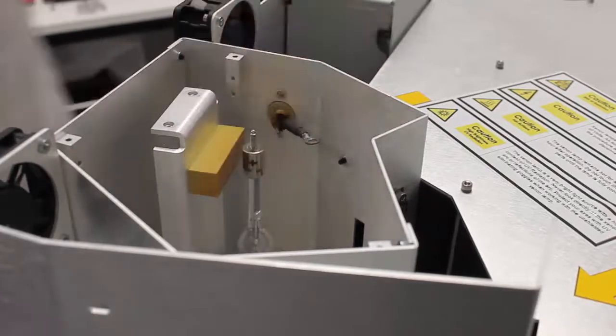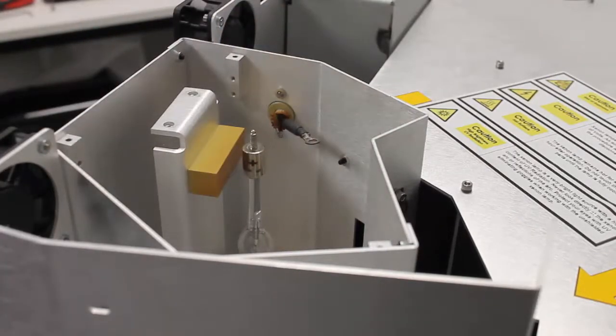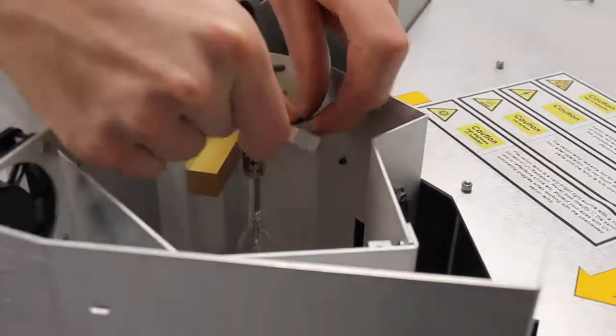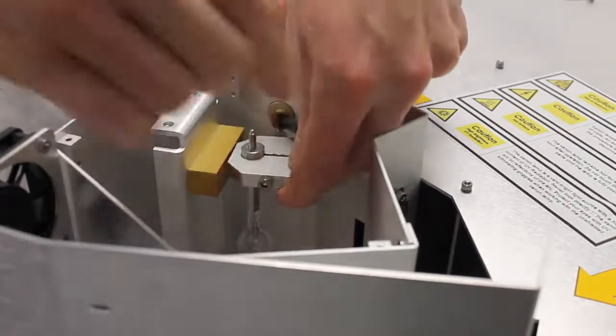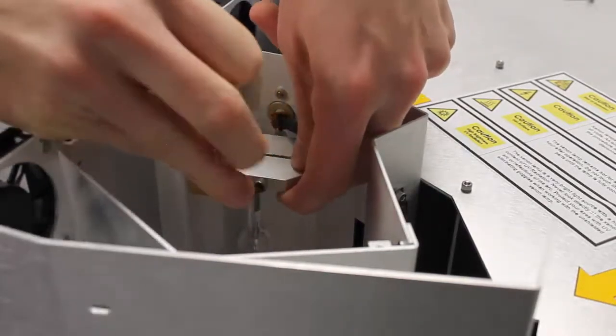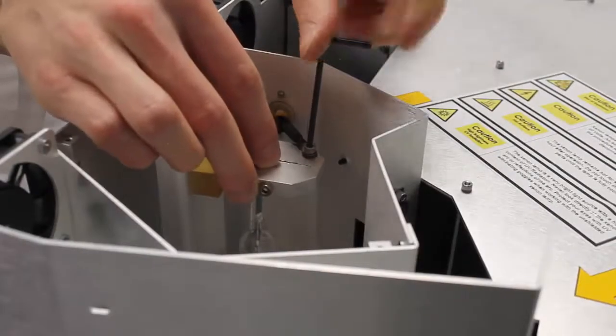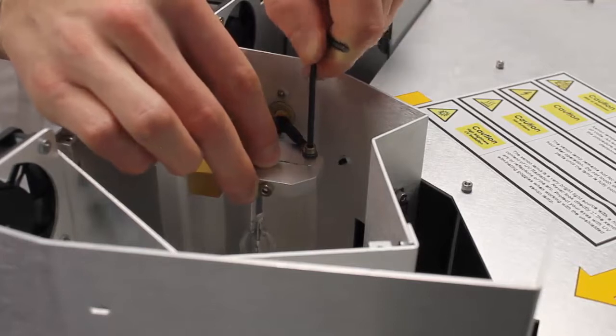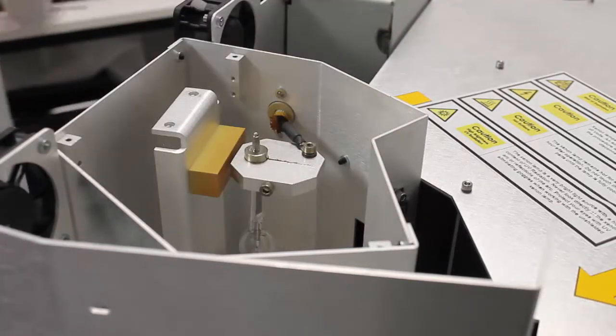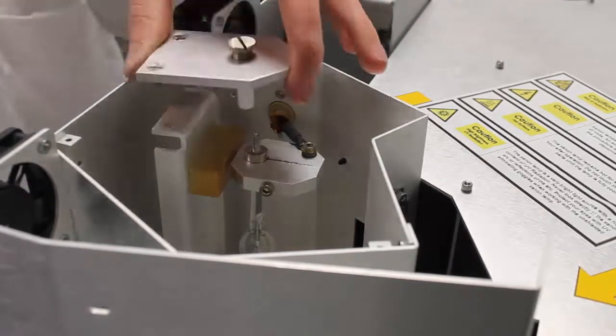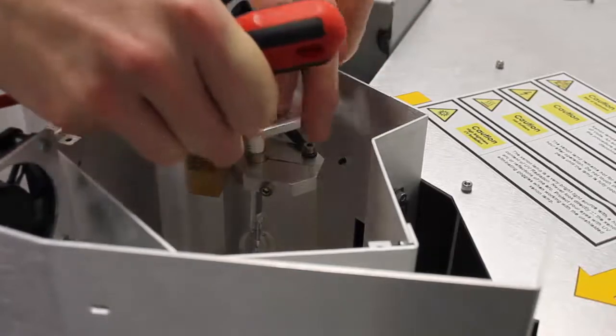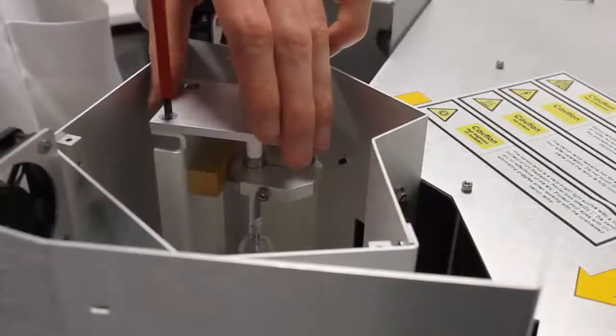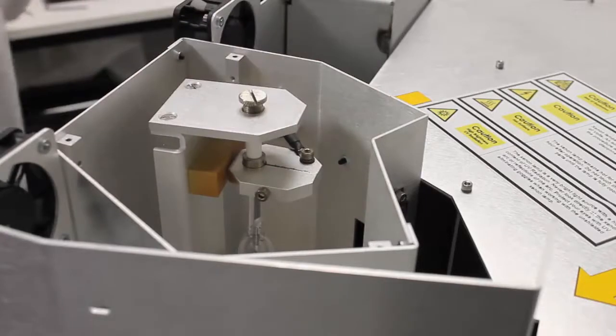The cathode support is connected to the new bulb and the new bulb is placed in, taking care to ensure that the wire down the side of the bulb does not interfere with the beam path. The anode support is then placed on and connected, and finally the vertical retainer is screwed on, and the lamp cavity lid is then attached.